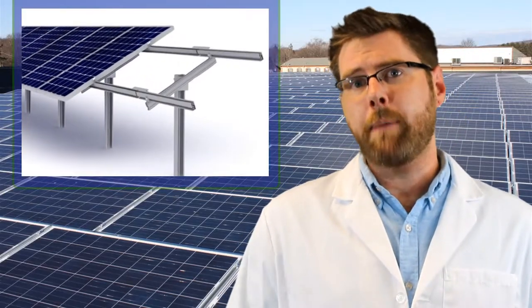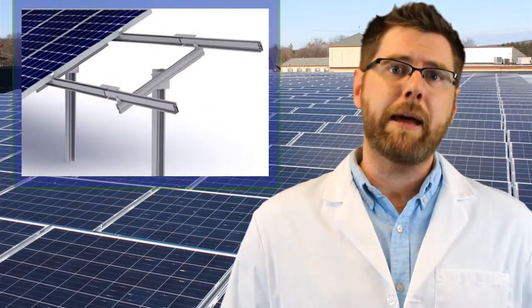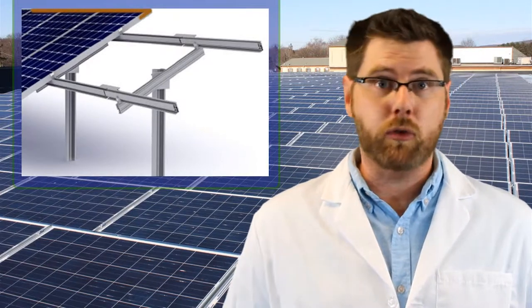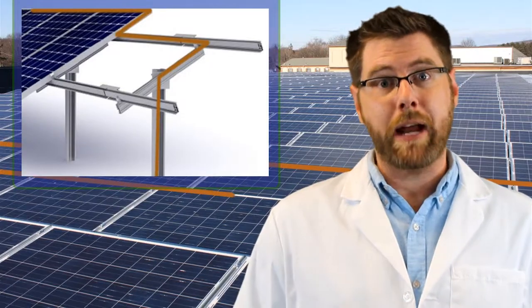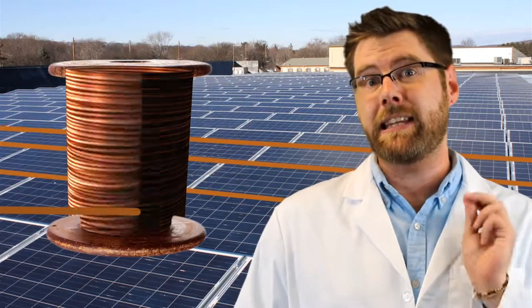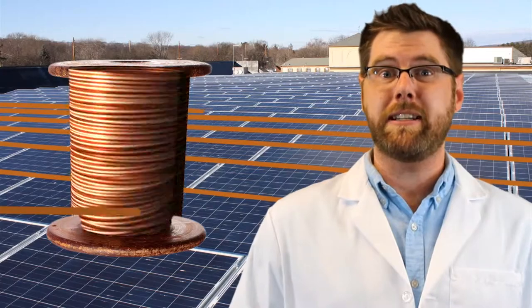Traditionally, grounding is accomplished by running a copper wire to every exposed piece of metal on a PV array. That includes your racking system and your module frames. That copper wire is attached to racking and module frames via a lug. This can be time and labor intensive and does require a lot of copper wire.